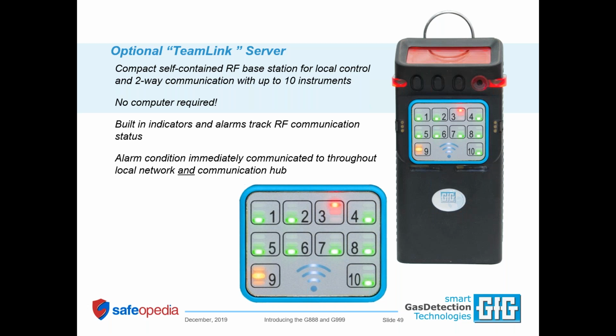You can see readings from any instrument, and if you want to clone the display from a particular instrument, all you have to do is go to that instrument. The icons on the front show you if there's an alarm on that channel and the communication status of that channel. You don't need a computer—if you don't want a base station, you don't have to have one or an additional base station. The Teamlink is your base station.